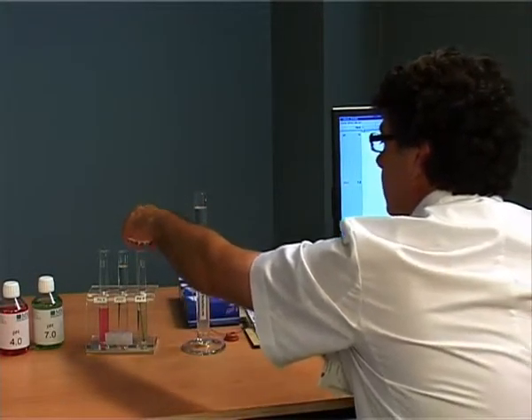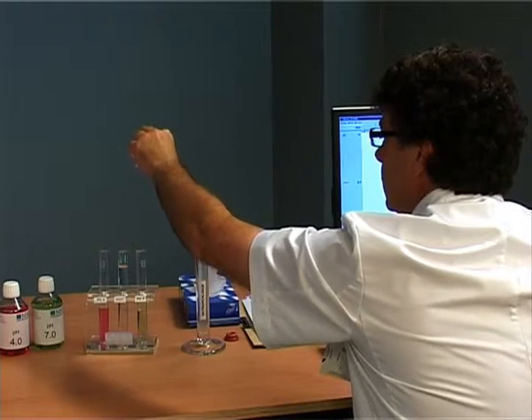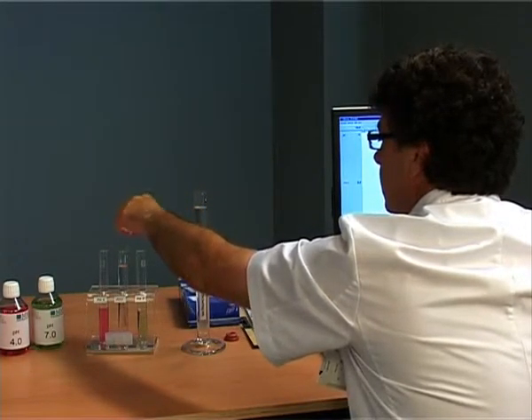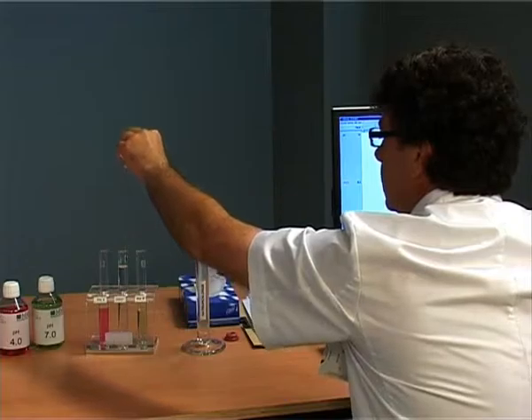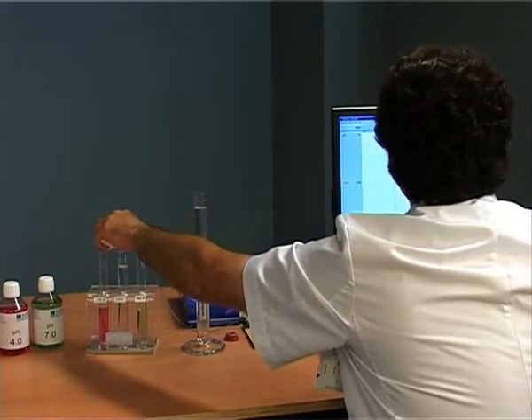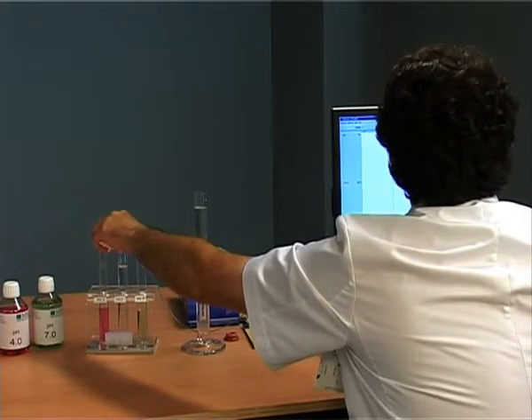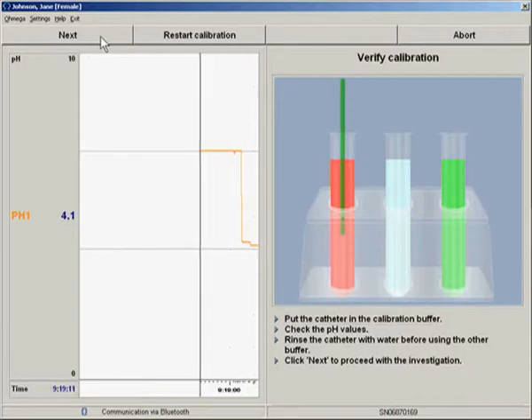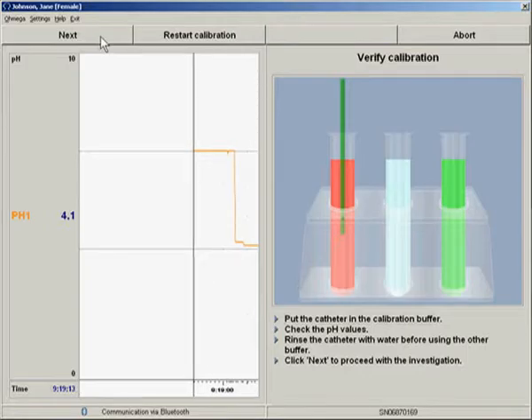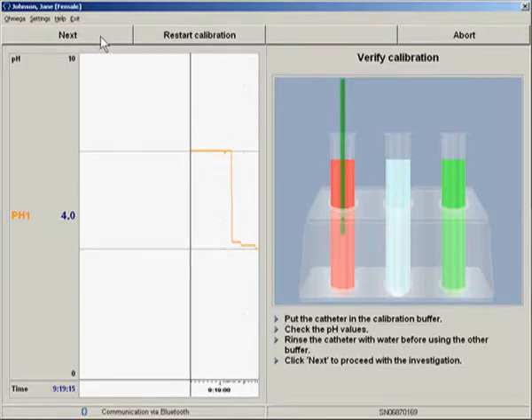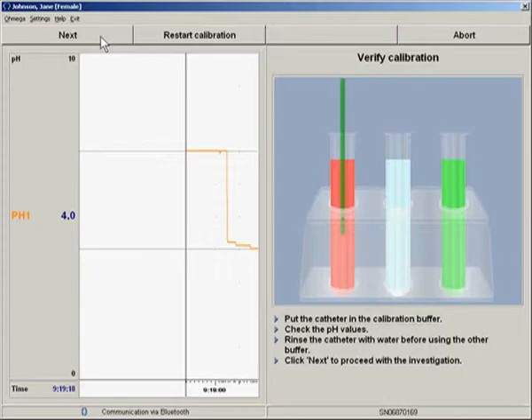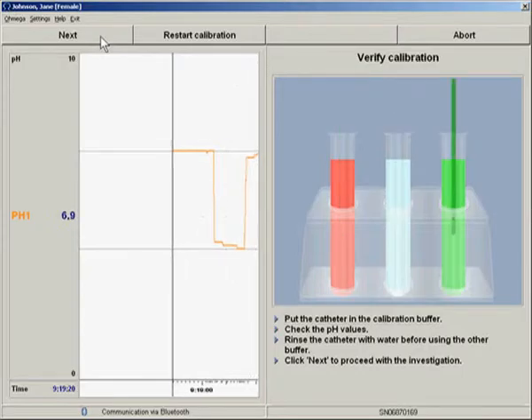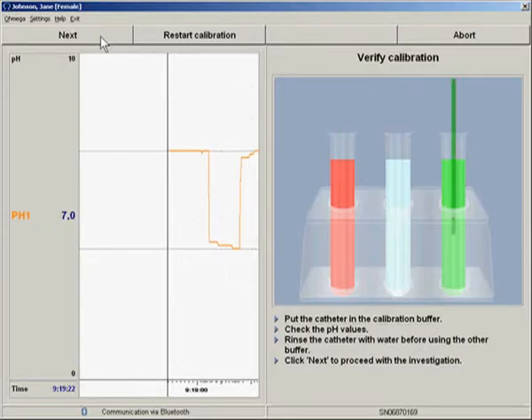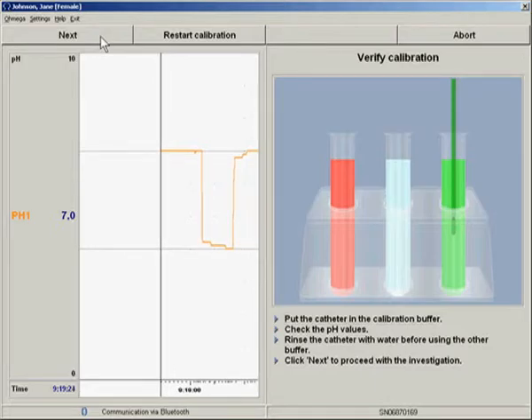After ending calibration in buffer solution pH 7, the quality of the calibration can be verified. Place the catheter alternately in each buffer solution and check the reading of the pH value. The VIP program shows the pH values on the screen. The reading in the red buffer solution is pH 4. The green buffer shows pH 7.